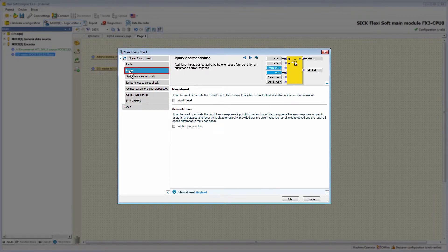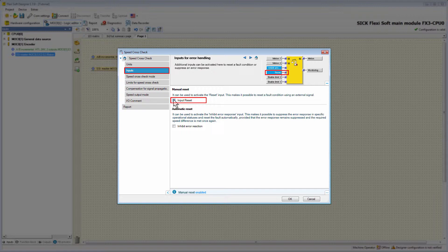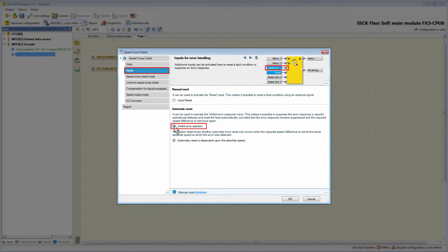Let's move to the tab Inputs. Here it's possible to enable additional inputs for error handling. These inputs can be used to reset the system if the output MonitoringStatus goes low because the allowed relative speed difference is exceeded. To reset this kind of error there are two optional ways: first, with the input Reset, which enables a manual reset — an error can be reset by rising edge if the speed is zero. Second, with the input InhibitErrorReaction, it's possible to realize an automatic reset. If there is a high signal at InhibitErrorReaction, indicating that the hazardous area is not accessible, then no error will be triggered, and occurring errors are reset automatically when the encoder signals match each other.